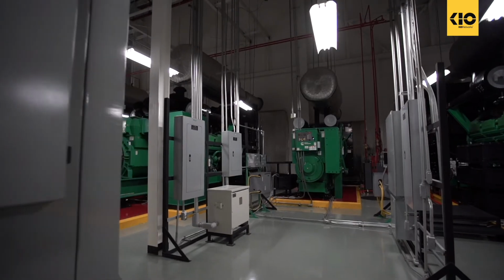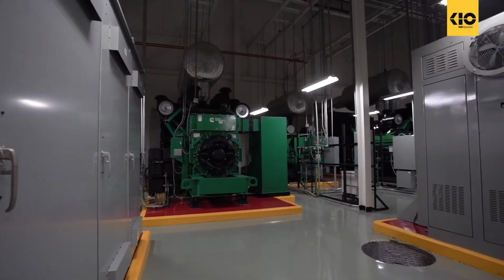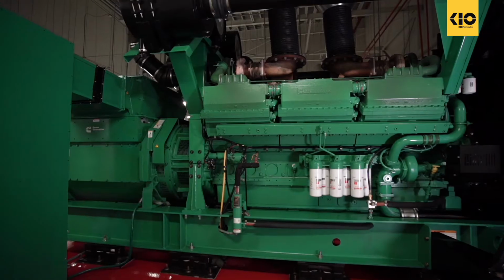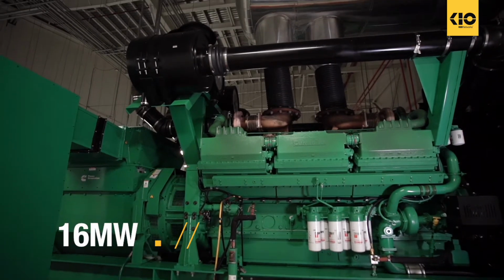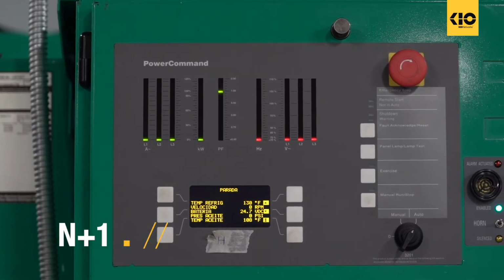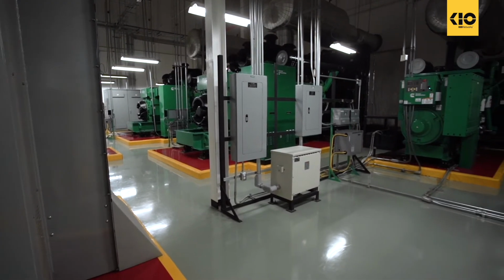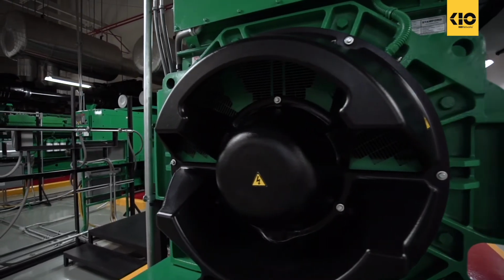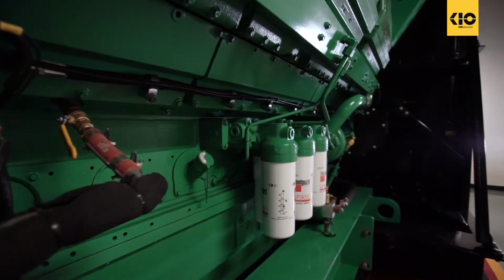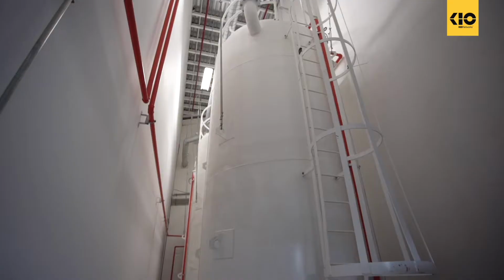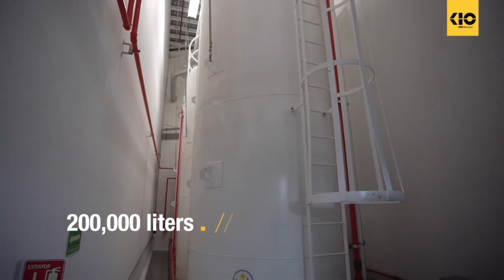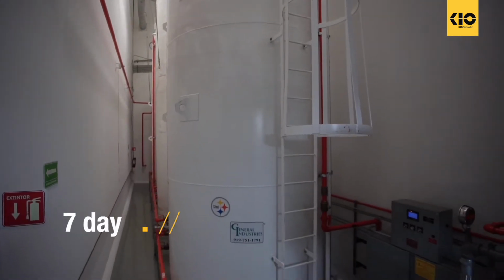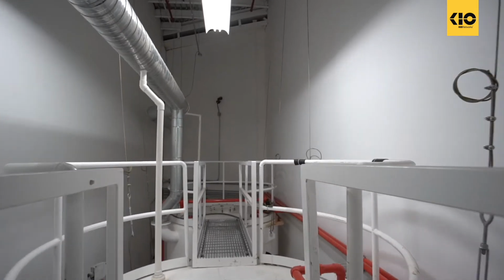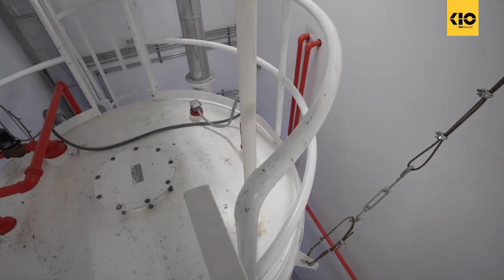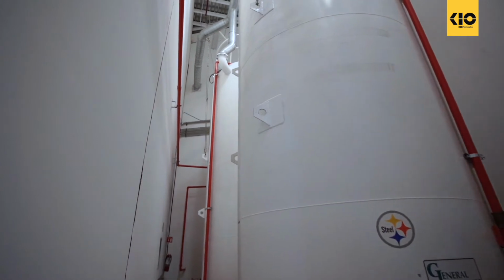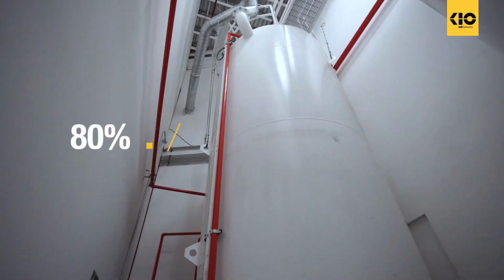These generators automatically turn on when they detect a loss of voltage from the commercial network provider. It has a generation capacity of 16 megawatts with an N+1 redundancy topology. We have to mention that the generators can operate continuously to ensure the availability of energy during any contingency in the utility power network. We have diesel tanks with a capacity of 200,000 liters, which allow us an autonomy of 7 days without refueling. Furthermore, we maintain diesel supply contracts with 2 different suppliers that can provide a service on the same day of request to always keep the level of the tanks above 80%.